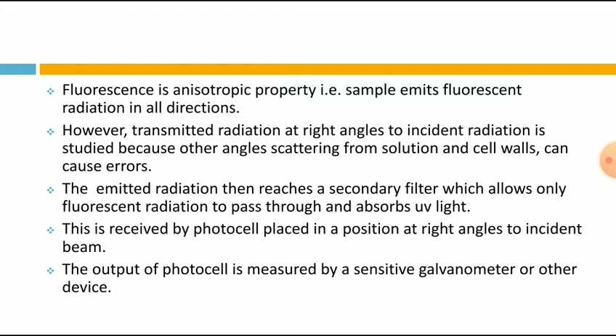Now we will see the schematic diagram of the single beam fluorimeter. This is the diagram of the single beam fluorimeter. Now again we will see all the components of the fluorimeter. What is the first component that we have already seen? The radiation source, that is the mercury vapor lamp. This is the collimating lens. This is the primary filter. This is the focusing lens. This is the sample holder, which contains our analyzing sample. The second is the collimating lens, secondary filter, focusing lens. This is the photomultiplier tube, or we can say photocell. This is the detector. This is the readout system. These are all the components of the single beam fluorimeter.